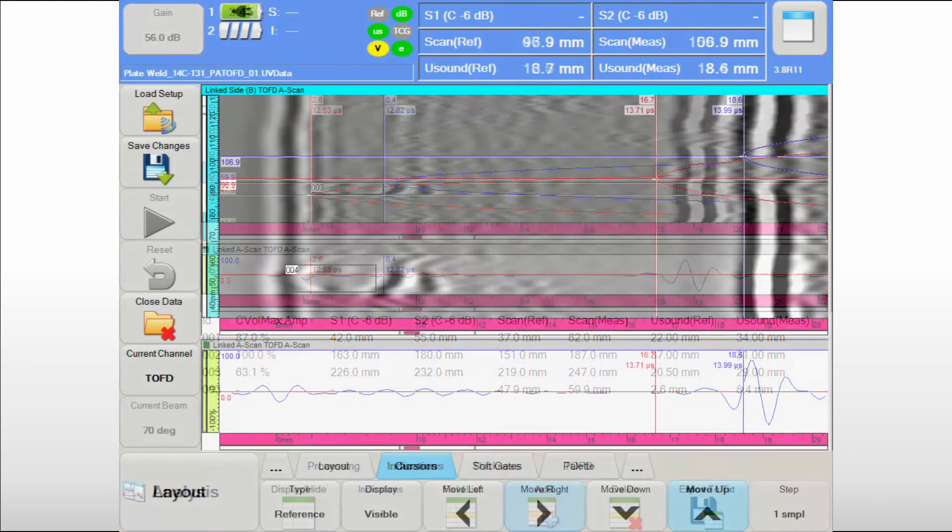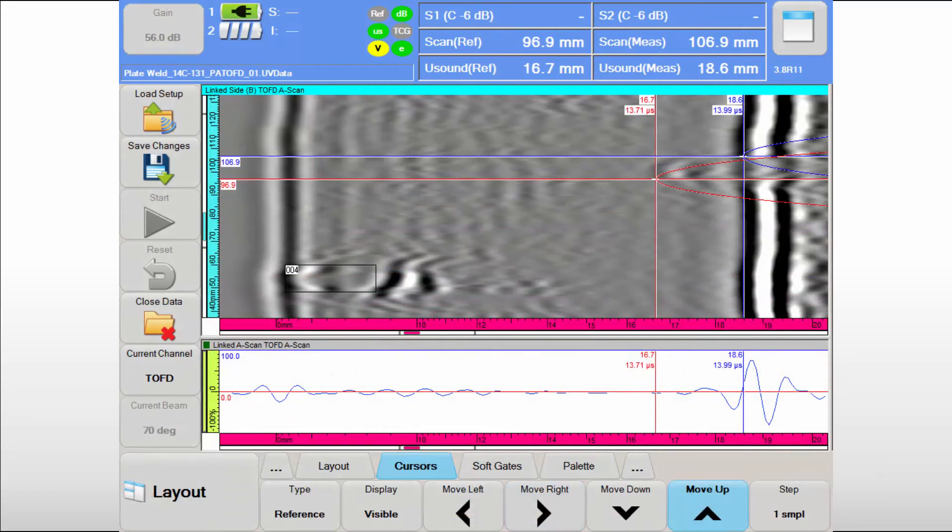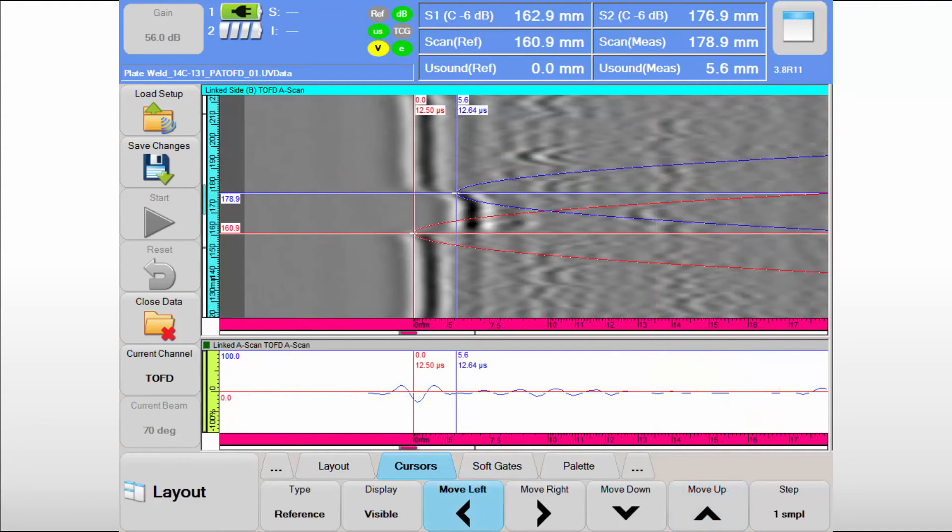Using the same simple technique, a 2 mm high incomplete penetration at the weld root is accurately measured at 1.9 mm. Finally, the toe crack at the near surface is also detected with TOFD, and accurate length and through wall sizing information can be obtained.